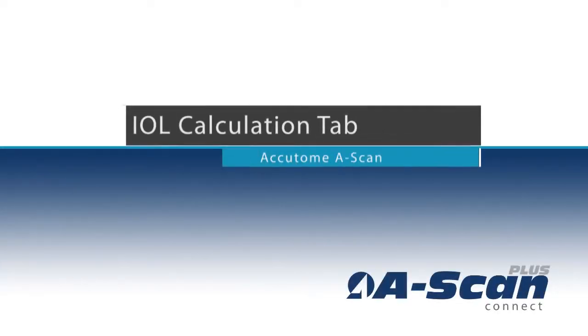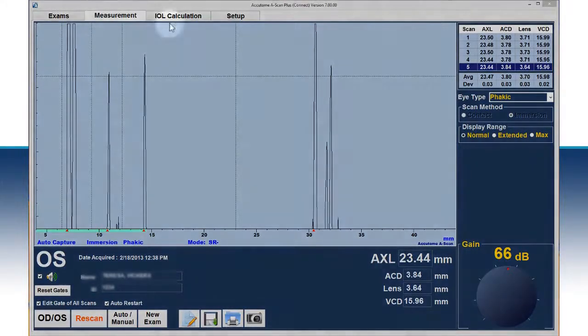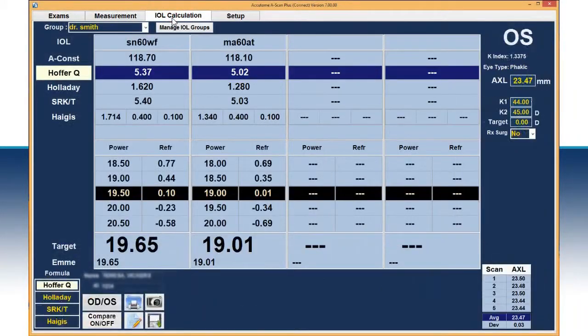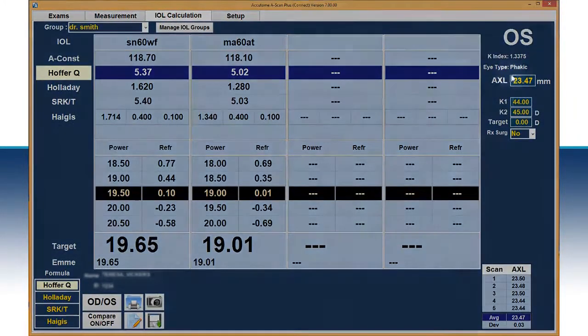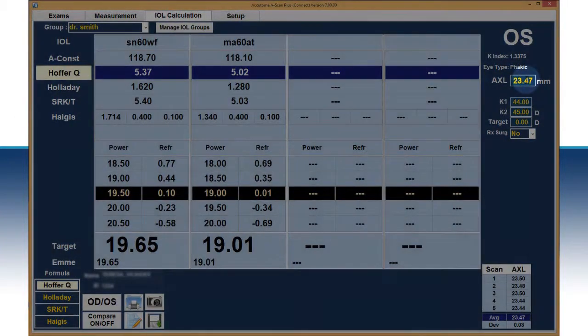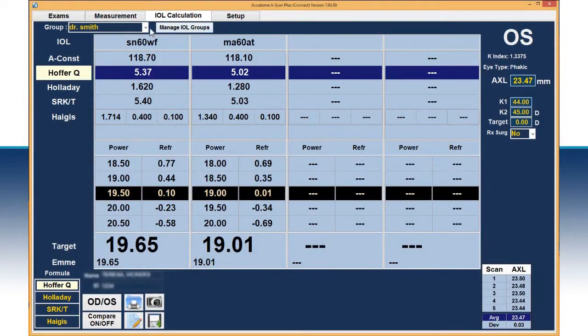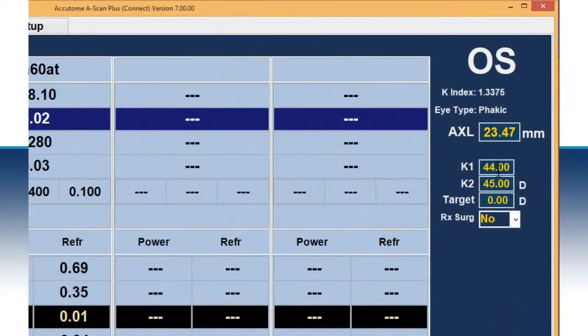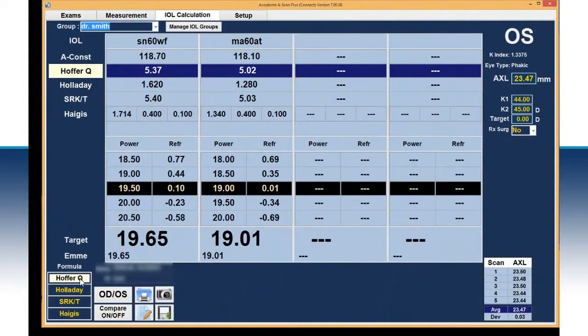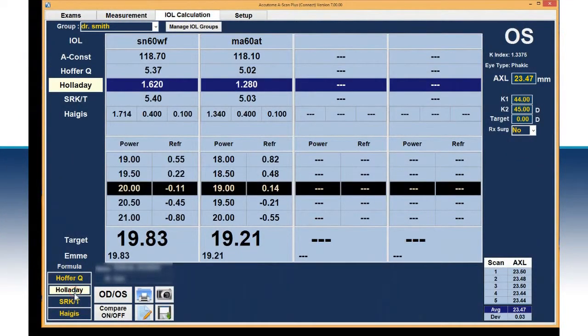Once the scans are completed, select the IOL Calculation tab. The average axial length will automatically be transferred to this screen. Select the appropriate IOL group. Input the K1 and K2 values. Make an adjustment to the refractive outcome target, if desired. Select the appropriate calculation formula. The IOL power recommendation will appear in bold for each lens.